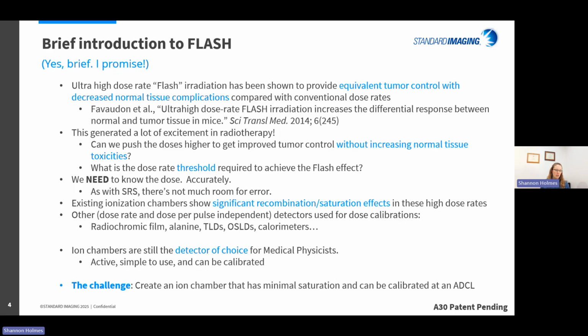And in order to really ensure that that's happening, we need to know the dose from these beams, and we need to know it accurately. So as with the single high dose fraction treatments like stereotactic radiosurgery, SRS, there's not much room for error here. We need to have accurate measurements for these doses. Ionization chambers that are already on the market, as I'm sure all of you know, have significant recombination and saturation effects that show up in these ultra high dose rates. So most people are turning to other dose rate or dose per pulse independent detectors for their beam calibrations, using radiochromic film, using alanine, TLDs, OSLDs, even calorimeters. If you're at the National Standards Labs, they're a little more proficient with that than some of us out in the field, unless you can get the graphite probe from the, is it the NRCC.